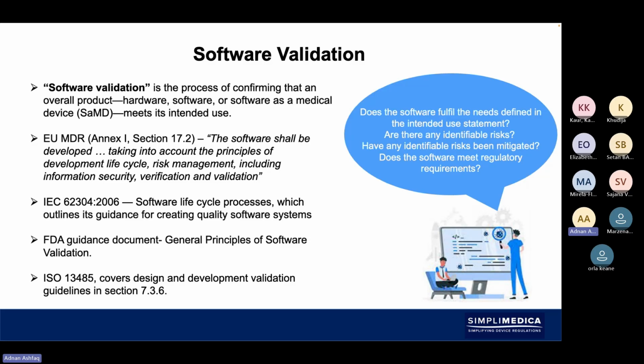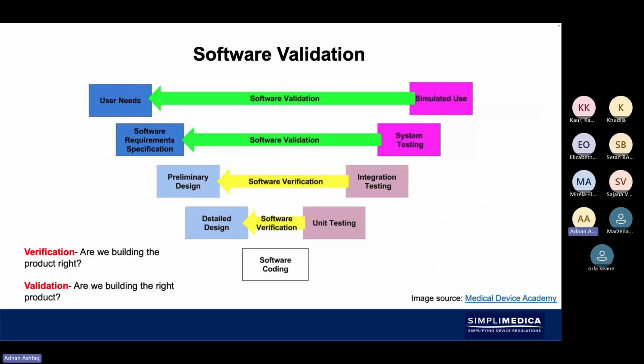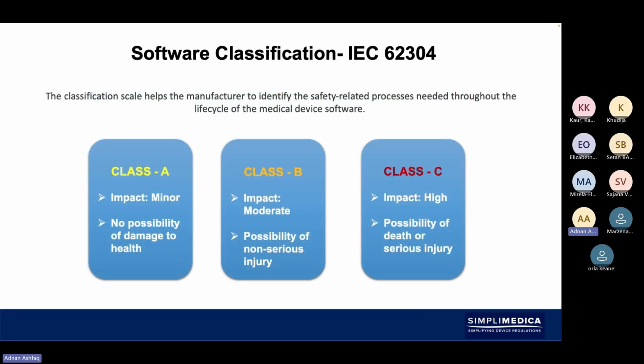With software validation, you need to follow 62304. Look also at the FDA guidance, General Principles of Software Validation. The EU MDR Annex 1 requires specific requirements for software validation. The V model is always a good model to have a look at for software validation. Look at your user needs, look at the software requirement specification, look at developing your design, and look at your detailed design. The software code needs to be tested. We need to verify and validate the testing, and we need to follow 62304.